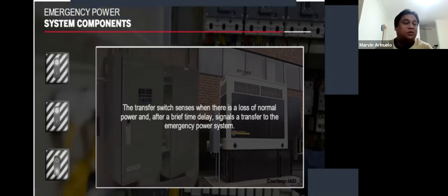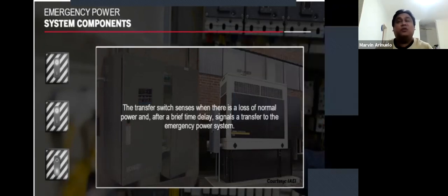Guys, very important, especially to our life safety devices system, that in case there is trouble or an issue with the primary source of power, we can still use our life safety equipment or devices because we have an alternative source of power, especially in our pumps, in a pump room. So power interruption or loss might not be an issue, because we have an alternative source of power. And one of that is your automatic transfer switch to your UPS or uninterruptible power supply.